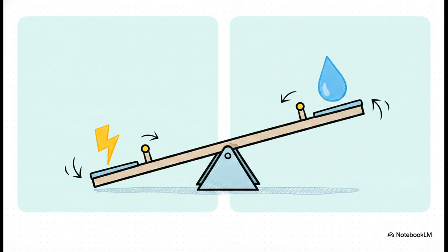If you use highly efficient water-cooled condensers, your power use drops, giving you an awesome PUE. But your cooling towers evaporate millions of gallons of water, severely spiking your WUE. On the other hand, if you switch to air-cooled condensers to save the local water supply, getting that amazing WUE of 0, your compressors have to work so much harder in the summer heat, completely ruining your power efficiency.